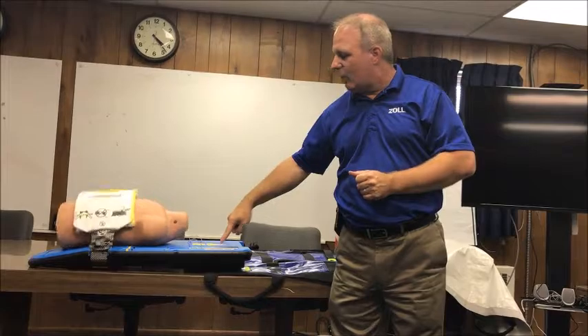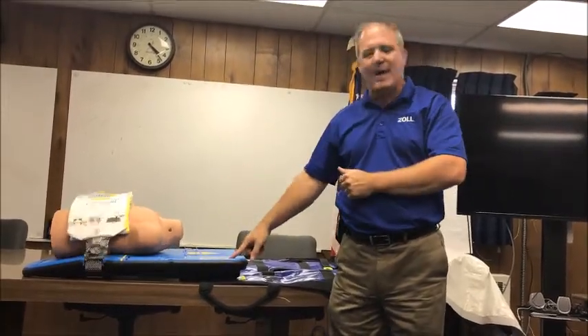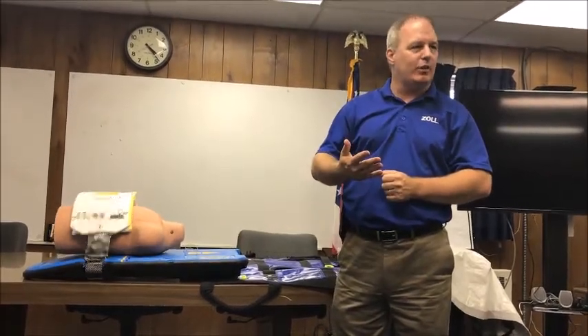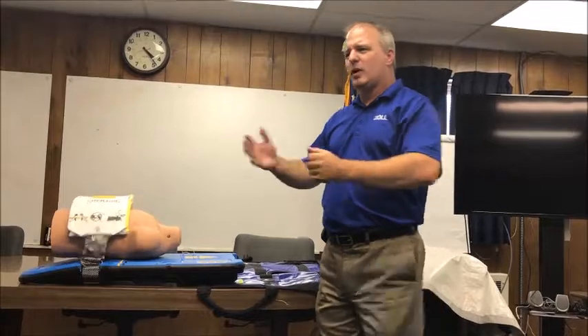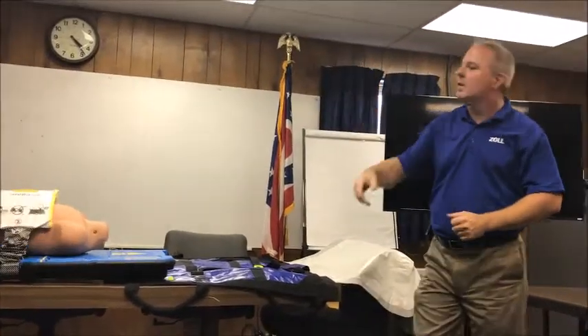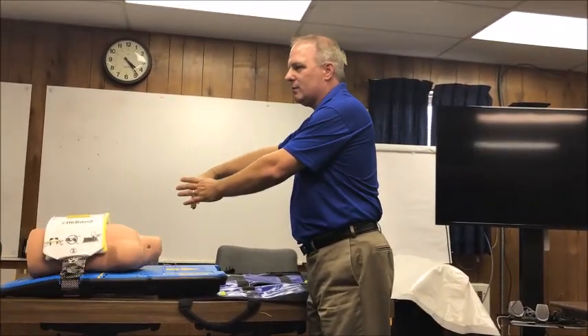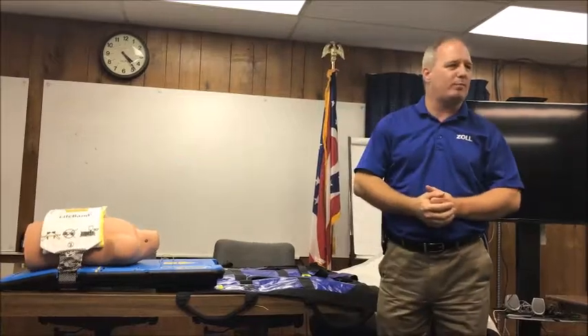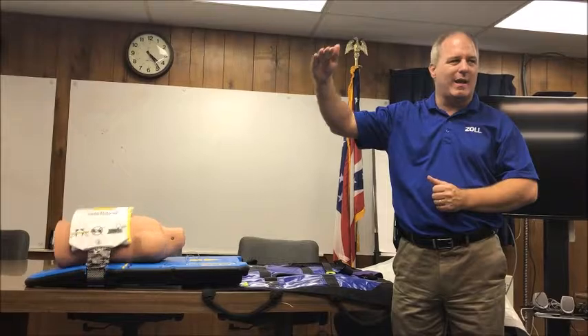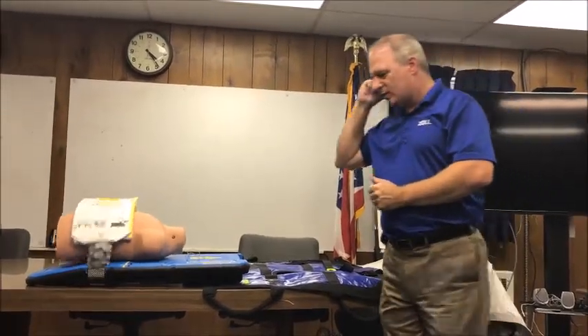Again, the lights only illuminate when there's an option. So we're moving. I'm not going to have a green light. The only thing I can do is stop. We have it set to 30 to 2. Just like when you're carrying someone down the steps, you normally count 3, 2, 1, ventilate, exhale, ventilate, and right when you're ready to exhale, the AutoPulse picks back up. The beeps are chest compressions, 28, 29, 30, pause. So we'll give it a chance to do its thing.